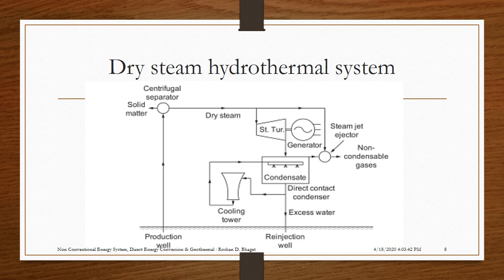The figure shows the dry steam hydrothermal system. This system is similar to a thermal power plant used for generation of electricity. Instead of using coal as fuel, heat from the earth is utilized for generating steam. The purpose of the centrifugal separator is to separate out foreign particles coming out with the steam, which may reduce the life of the turbine if allowed to pass through.